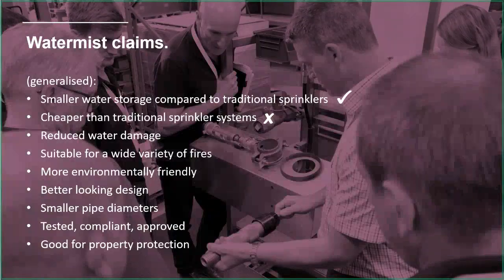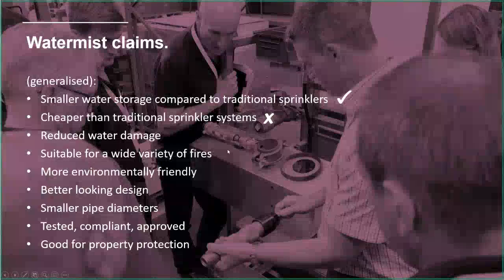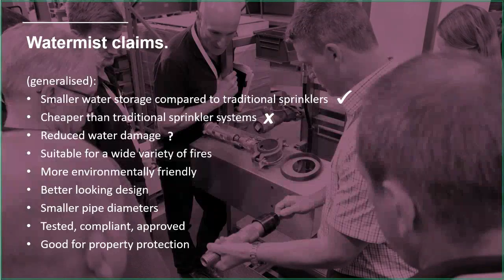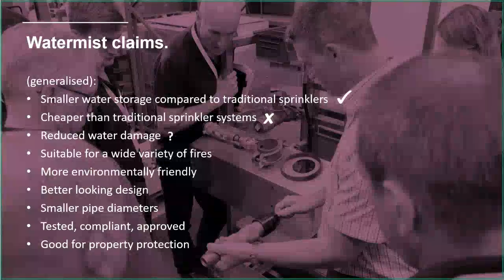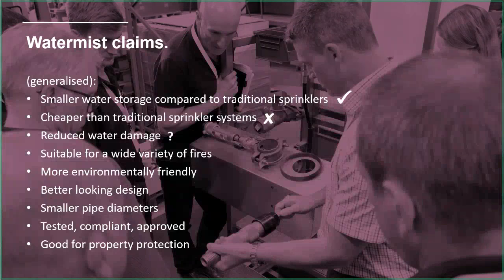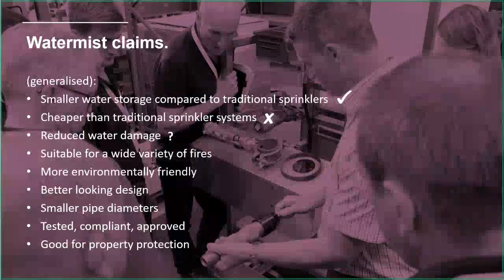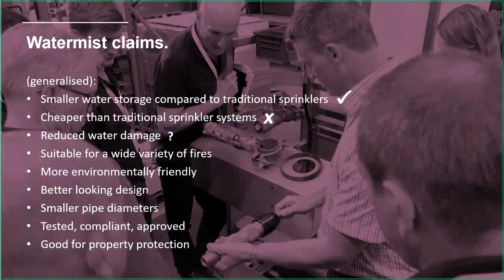Next one is about reduced water damage. Which... it's kind of true. Because you're discharging less water, water mist manufacturers will say there's going to be less water damage. In the case of an accidental release of water, yeah, I'd say that's true—the less water you discharge, as long as you get to it quickly, you may end up saving some property damage.